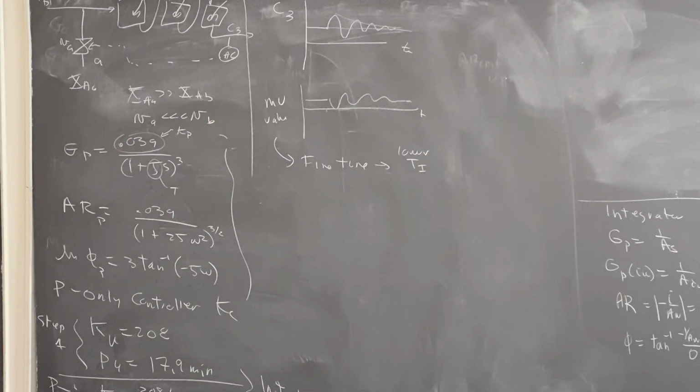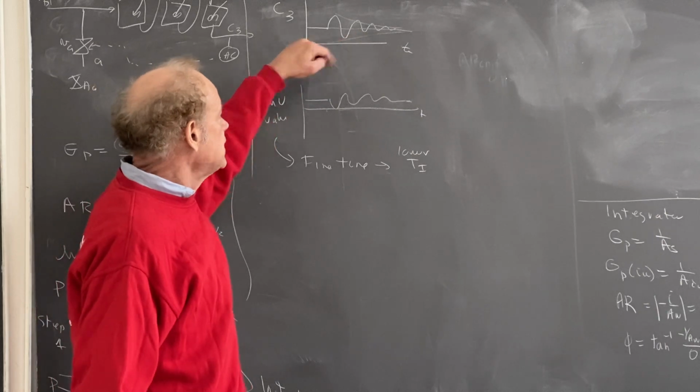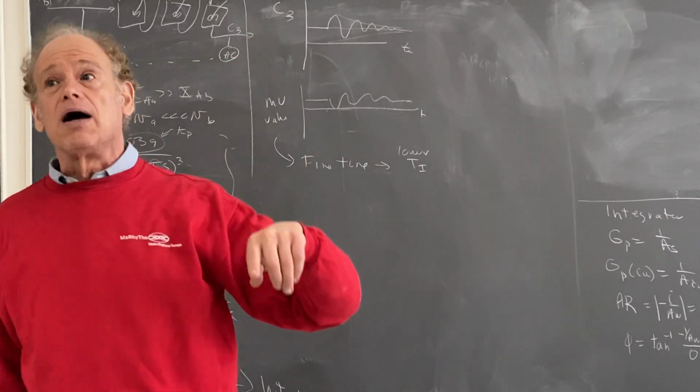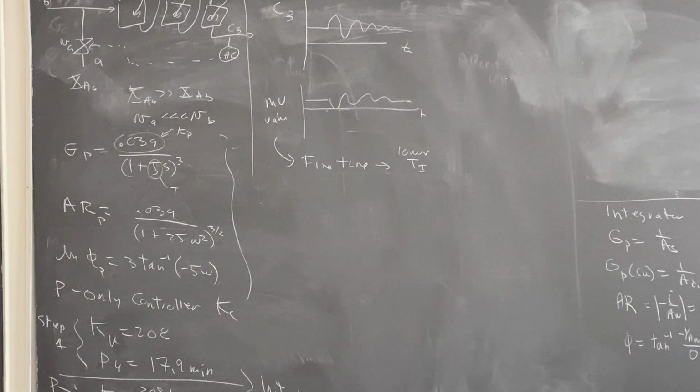Lower it a little bit at a time to make sure you don't make things unstable, till you have less oscillations to get to your set point. And again, you don't want these oscillations because they take too long, and because the manipulated variable, the valve, keeps going on and off, opening, closing, eventually it's going to break. So you don't want it to break. Are there any questions on that? Why don't we look at another example?